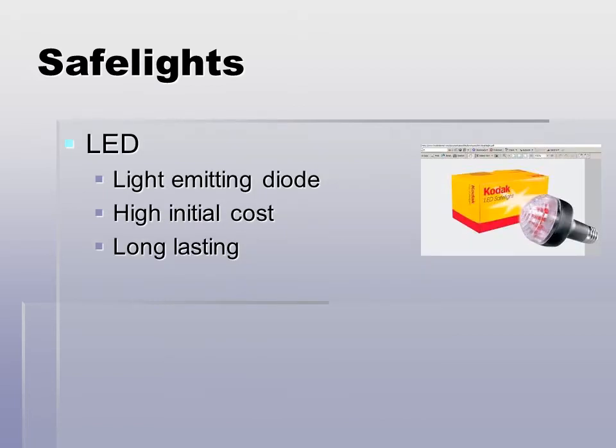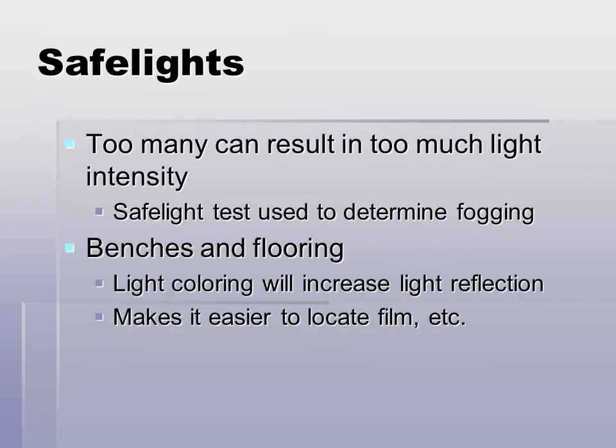The LED is one of the newer safe lights that are available. It is called a light emitting diode, which stands for LED. It has a high initial cost, but it is very long lasting. If there are too many safe lights, it can result in too much light intensity. So you do have to do a safe light test, which helps to determine the fogging on your films.